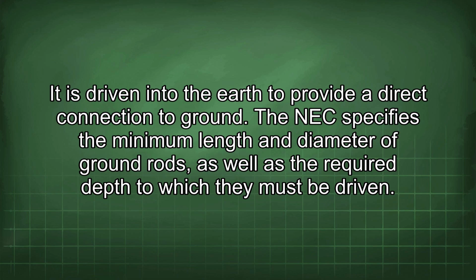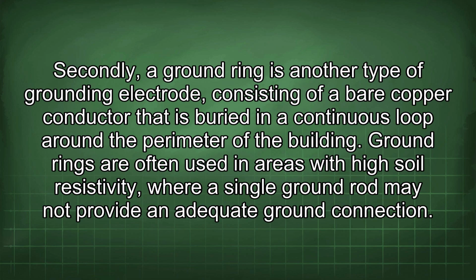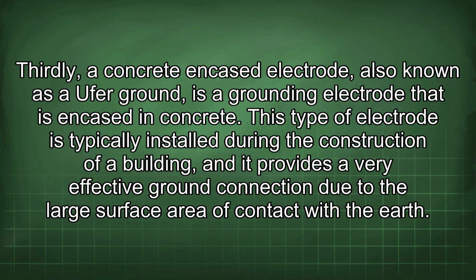must be driven. Secondly, a ground ring is another type of grounding electrode consisting of a bare copper conductor that is buried in a continuous loop around the perimeter of the building. Ground rings are often used in areas with high soil resistivity, where a single ground rod may not provide an adequate ground connection. Thirdly, a concrete encased electrode, also known as a UFER ground, is a grounding electrode that is encased in concrete. This type of electrode is typically installed during the construction of a building, and it provides a very effective ground connection due to the large surface area of contact with the earth.